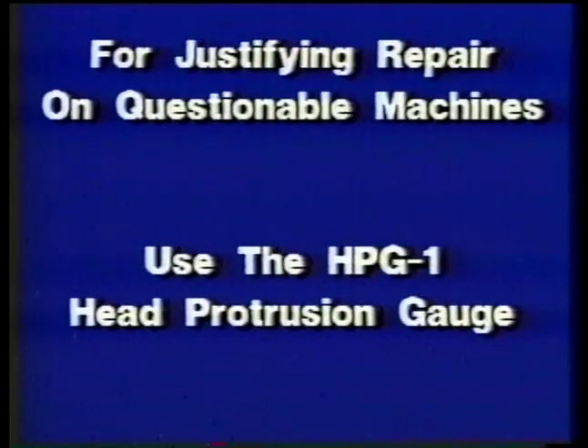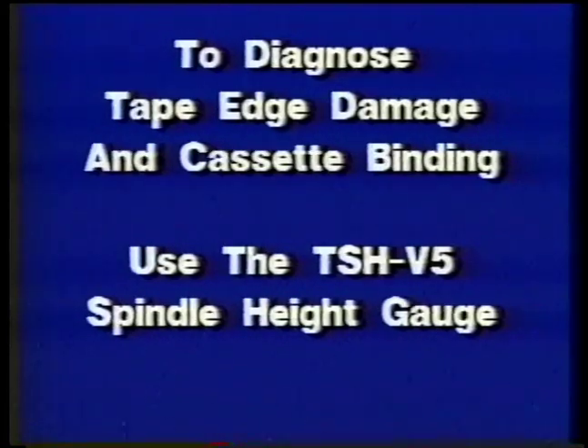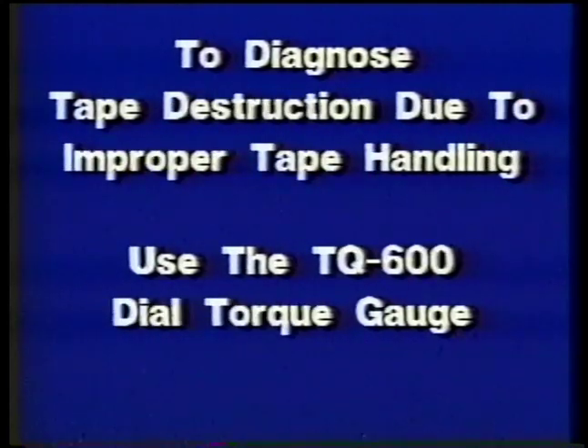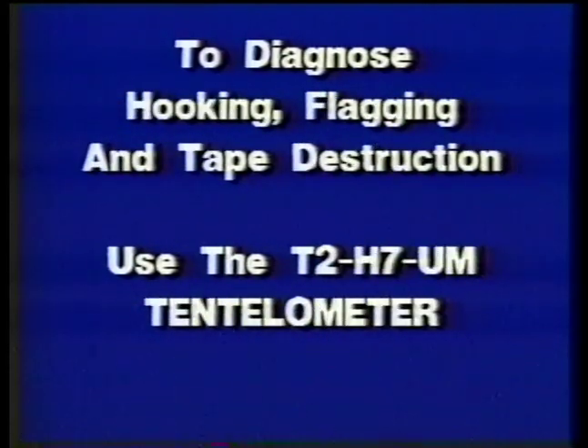The dynamics of these 4 gauges would be if a machine was questionable as to whether or not repair was justified, first check it with a head protrusion gauge to see if the machine is going to be worth repairing. Next, check the machine with the spindle height gauge to make sure that there's no edge damage problems or cassette binding problems in the machine. Next, the use of the torque gauge will show various torque problems caused by clutches, brakes, and motors in the machine that would cause tape destruction. And of course, the tentelometer is still the best way for measuring the holdback tape tension to prevent hooking and flagging and tape destruction problems in the machine.